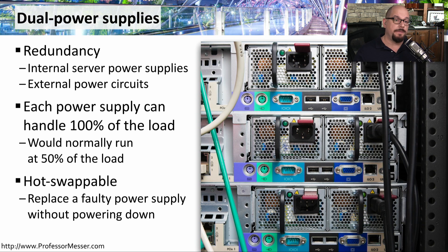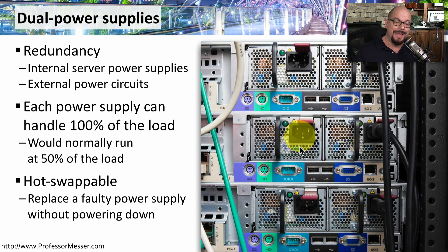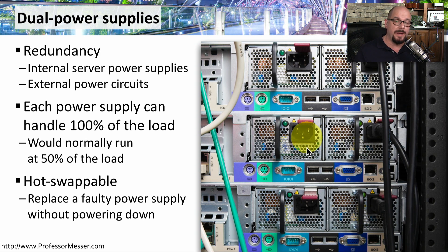In a properly configured dual power supply setup, you would not only have multiple power supplies, but you would connect one power source to one power supply and another live power source to the other. That way, if either power supply fails or someone disconnects one, the other power supply will keep the system up and running.